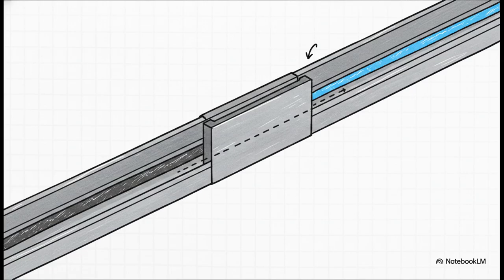First, there must be a minimum 50mm physical air gap from any non-IS circuits on a cable tray. If you can't manage that distance, they have to be separated by a solid earthed metallic partition. Also, IS and non-IS conductors absolutely never share the same outer cable jacket. No exceptions. And finally, to make sure nobody ever gets this wrong, terminals, enclosures, and cable sheaths must be marked light blue. It's a vital visual mnemonic yelling at everyone on the rig, hey, this is an intrinsically safe system, keep the high voltage away.